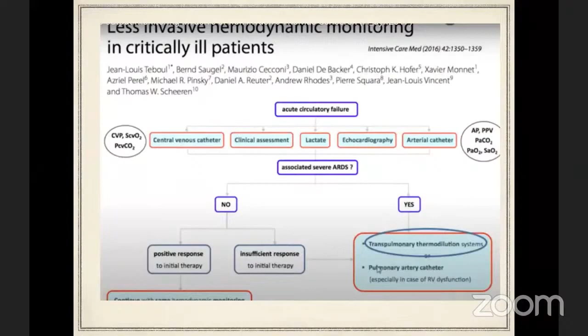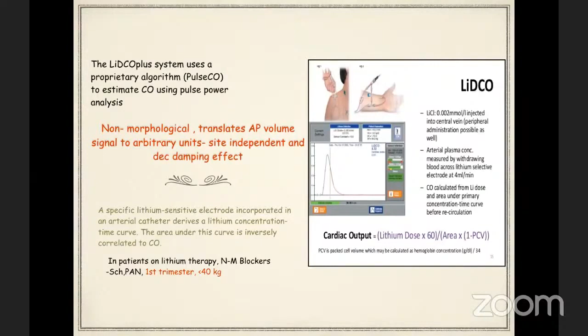transpulmonary thermodilution systems can improve the patient's outcome. Another system which comes into play is the LIDCO Plus system, and it uses not the pulse wave analysis, but the pulse power analysis, which is a non-morphological system which translates the arterial pressure volume signal to arbitrary units, and it is site independent. So we can use it at any site, not only major arterial catheters, and it has less of a dampening effect. But again, it comes with the contraindications that it cannot be used in the first trimester and in patients weighing less than 40 kgs.